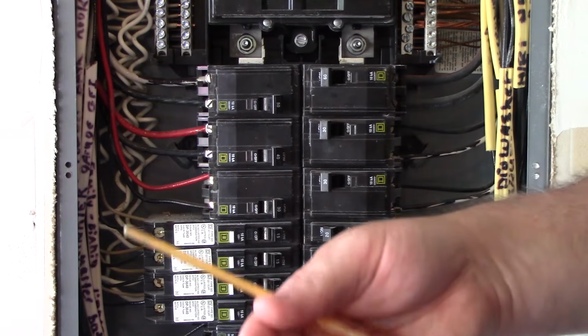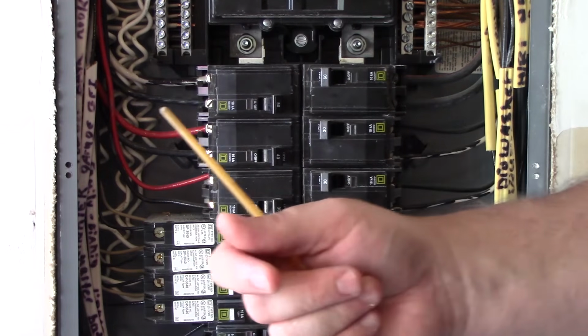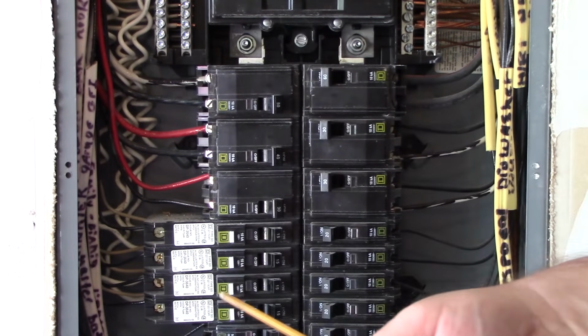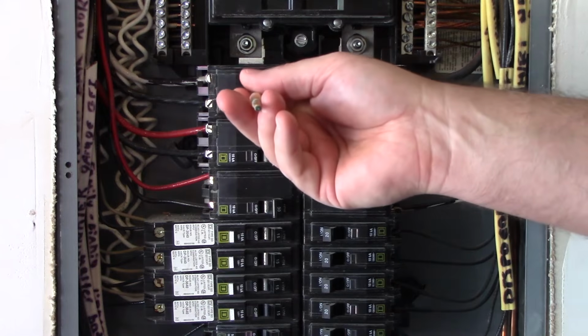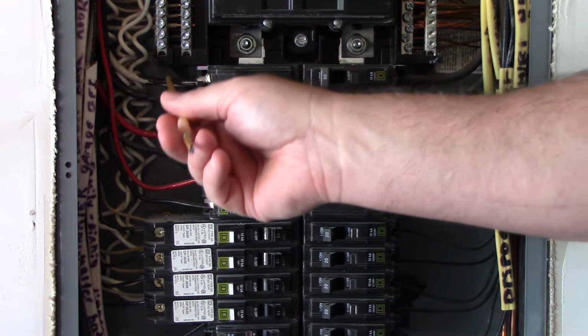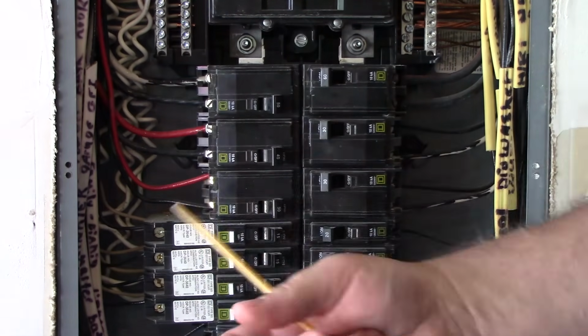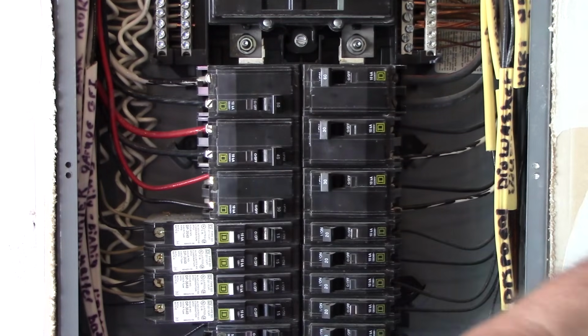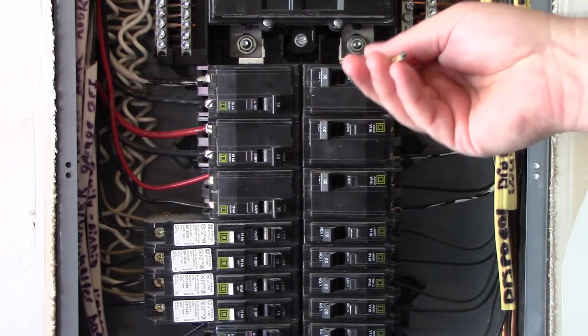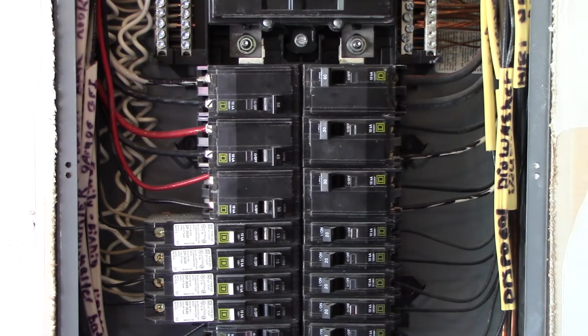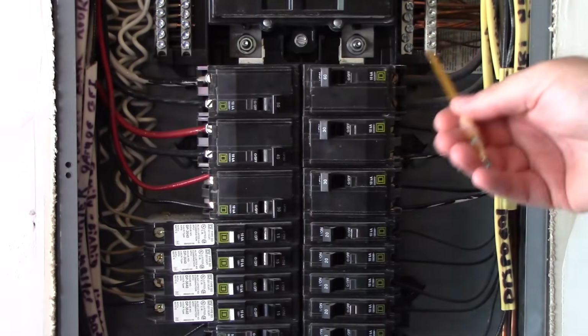Also, something to remember is you might have motors, you might have HVAC systems in here where it calls for a certain size overcurrent protected device, yet the actual branch circuit conductor might be smaller. And that's based on the nameplate. All right, so that's why we know this one's okay for the 60, because this is all based on the nameplate ratings and the circuit sizes.